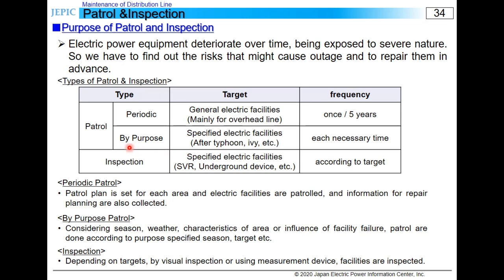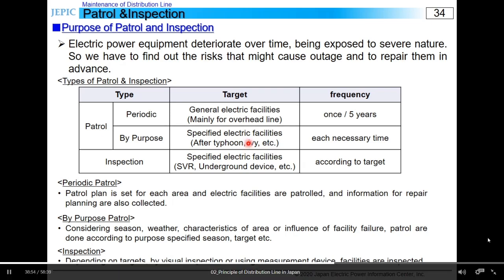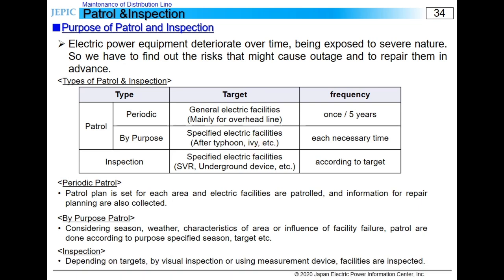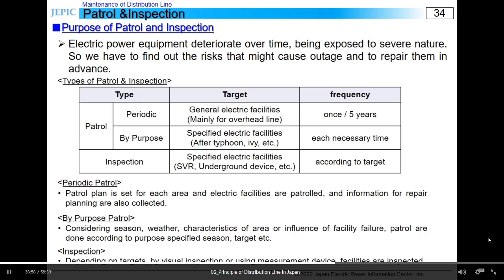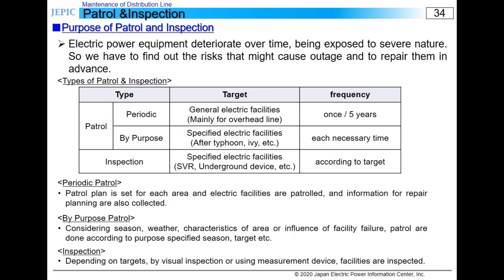By-purpose patrols are conducted as necessary, taking into consideration the season, weather, characteristics of the area, and the influence of a failure. For example, depending on the season, the ivy might grow up to the top of a pole, leading to a ground fault. A patrol for ivy is done from spring to summer. There are other cases such as a patrol for bird nesting, a patrol after strong winds, an emergency patrol in an outage, and so on.